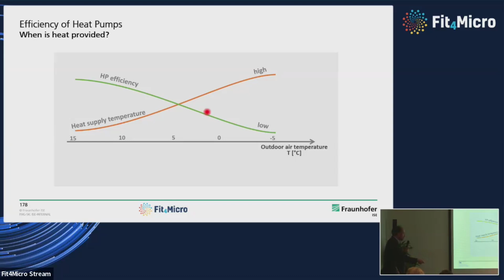So for the example of outdoor air temperature, if you look at buildings, it gets colder, the temperature you need to heat the building needs to be higher because you have a certain heat distribution, you have radiators, or even the floor heating needs to be at higher temperature if you have a higher heat load, which is influenced by the outdoor temperature. And at the same time, heat pump efficiency, due to two effects, goes down due to the source temperature, and it goes down due to the higher heat supply temperature. This is an important consideration when you look at when heat is actually provided.